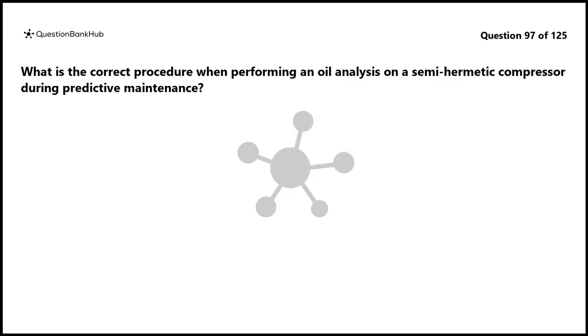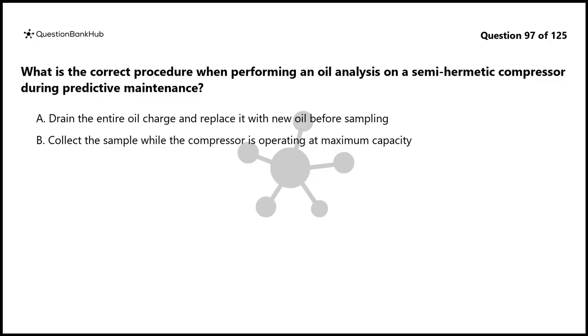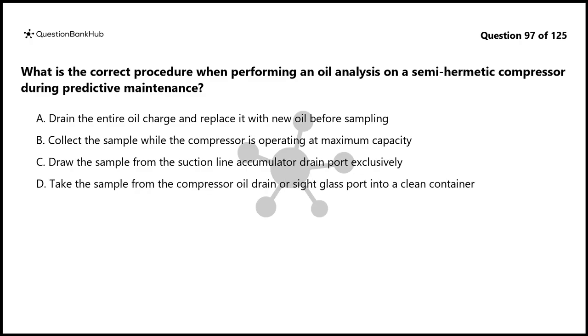Question 97. What is the correct procedure when performing an oil analysis on a semi-hermetic compressor during predictive maintenance? A. Drain the entire oil charge and replace it with new oil before sampling. B. Collect the sample while the compressor is operating at maximum capacity. C. Draw the sample from the suction line accumulator drain port exclusively. D. Take the sample from the compressor oil drain or sight glass port into a clean container.